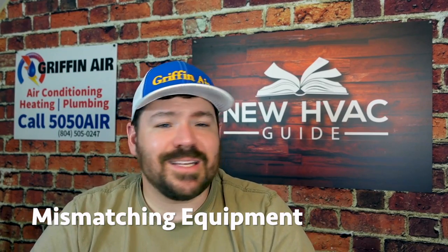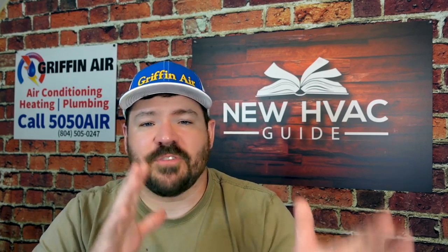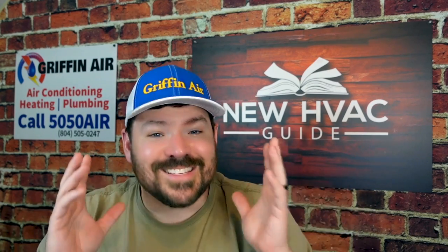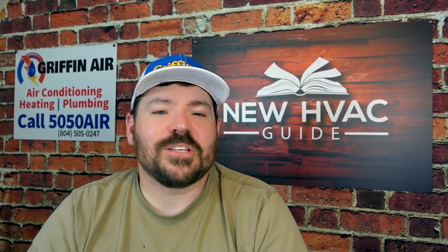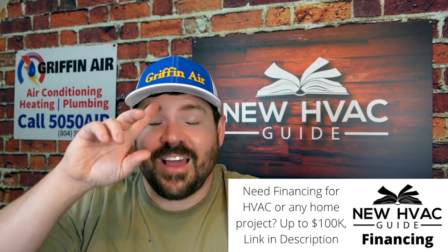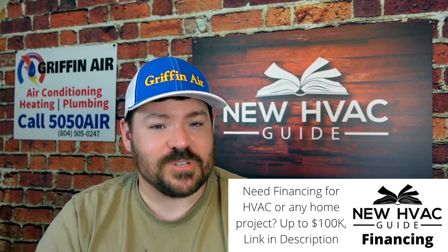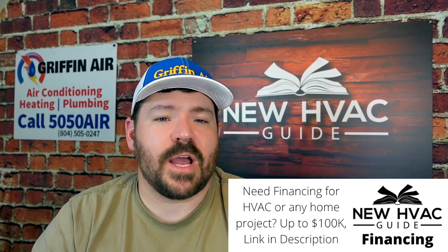Number two: mismatching equipment. This wasn't a big deal when I first got into the industry. I'd see systems that were different brands or different sizes in some cases. I've seen a 2-ton condenser paired with a 5-ton air handler, or vice versa, and of course they wonder why their compressor doesn't make it. If you've got a 5-ton condenser with a 2-ton air handler, you're definitely asking that compressor to do some special things.